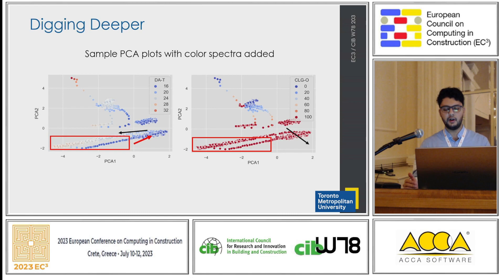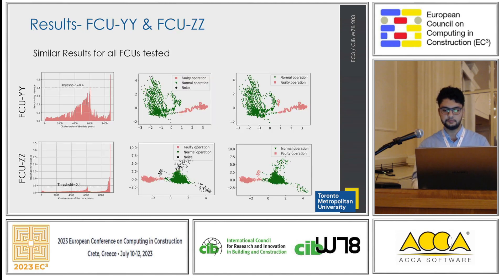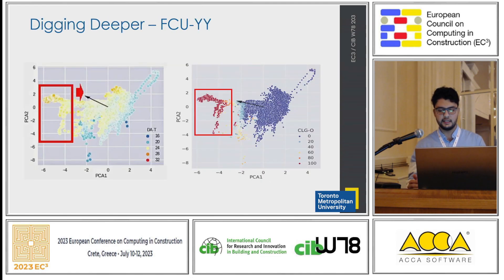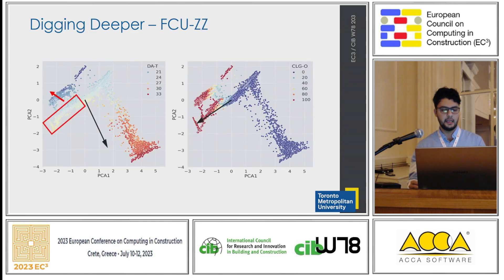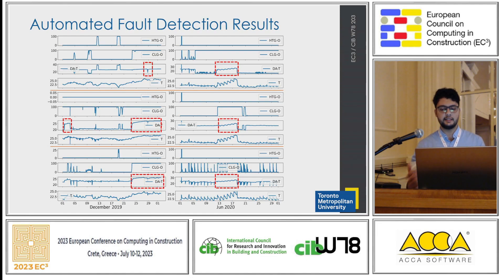To investigate the fault, we used color-coded PCA plots and added vectors to indicate the direction of change for each variable. Red arrows show the actual change, and the black one shows the expected change. The same process was repeated for the other FCUs — FCU-YY and FCU-ZZ. To better understand these faults, a PCA plot was consulted for FCU-YY and FCU-ZZ as well. These are extracts from time-series data analyzed during the peak heating season on the left and cooling season on the right, for FCU-XX on the top, FCU-YY in the middle, and FCU-ZZ at the bottom. The dashed box indicates the detected faults confirmed by the certified energy manager.